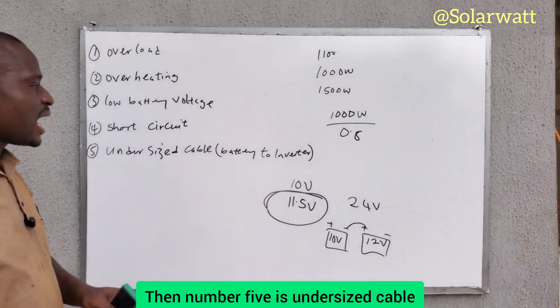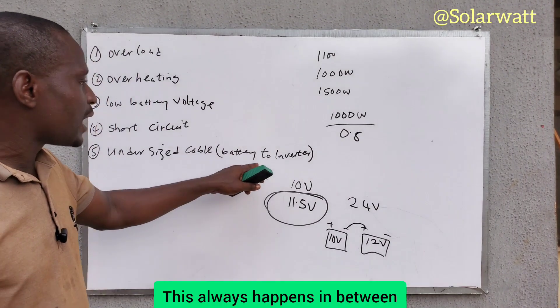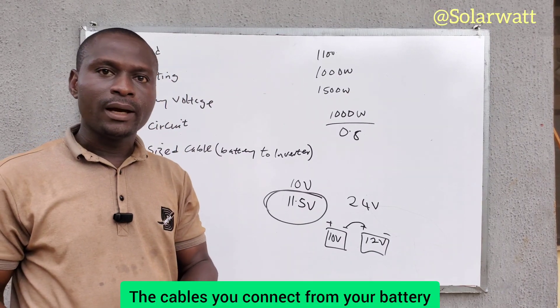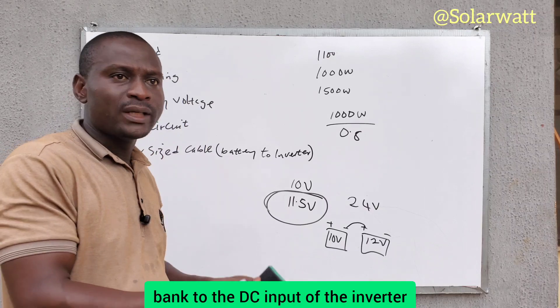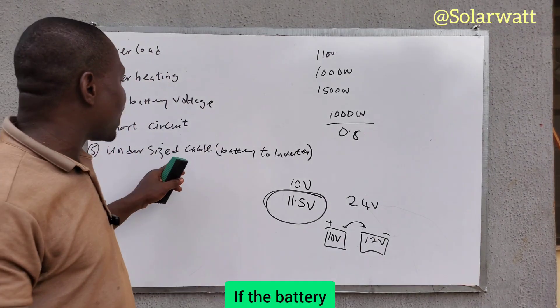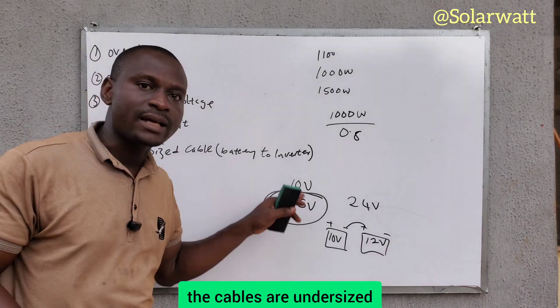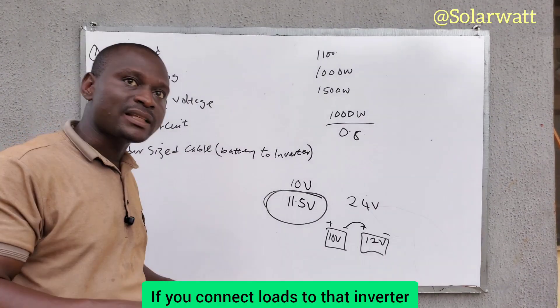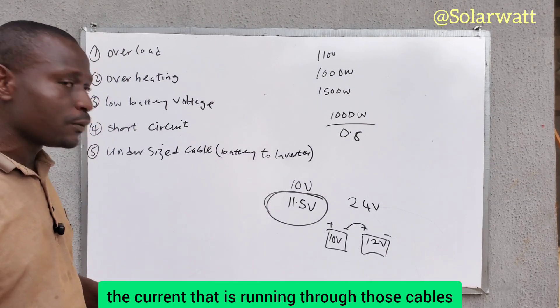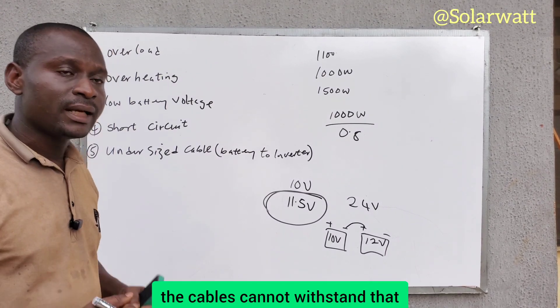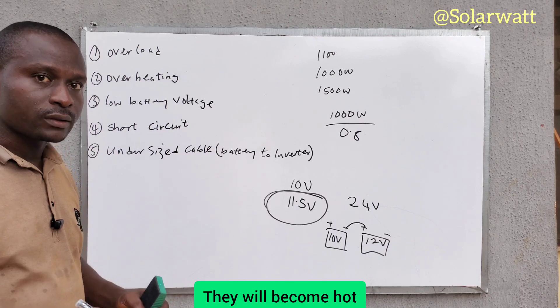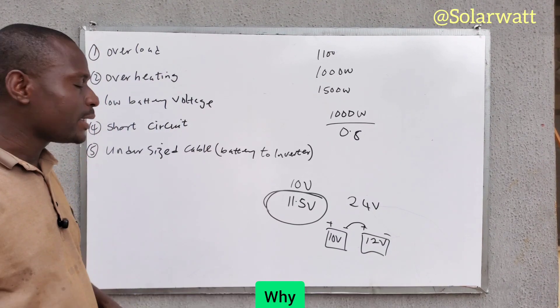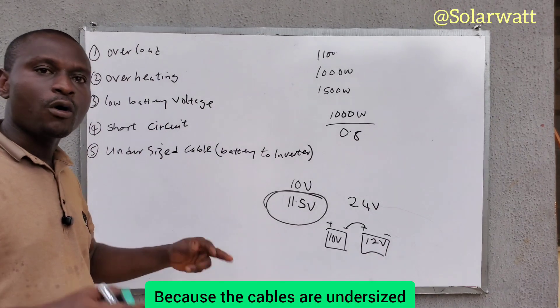Number five is undersized cable. This typically happens between the inverter and the battery bank — the cables connecting the battery bank to the DC input of the inverter. If those cables are undersized, the inverter will always be shutting down. When loads are connected, the current flowing through the cables exceeds what they can withstand, causing them to become hot. The inverter senses this and keeps shutting down because the cables are undersized.